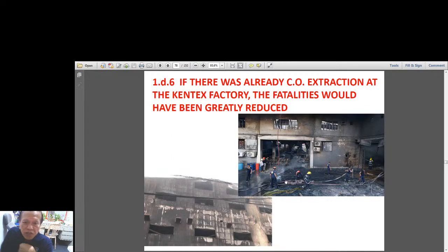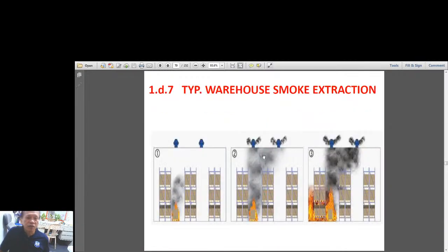And here's a picture of the ground floor of the Kentex factory building. The fire started here. There were flammable materials stored here that caught fire, and then the wind was coming inside the warehouse, suffocating the people inside the factory building. So even this kind of warehouse should also be provided with exhaust fans, exhaust ventilators like this one, so that if there is fire, you will be able to suck out the smoke. At least the people inside your warehouse will be able to run for safety.